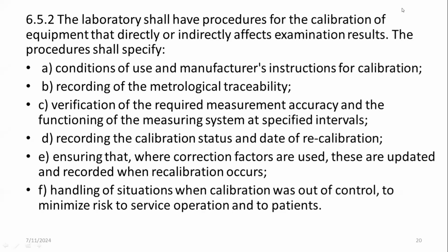So in summary, how this is supposed to be catered for is that once a calibration certificate is handed over to you, you're supposed to be able to determine what correction factors or correction values have been given by the calibration lab, and you should be able to use these correction values, as we shall see in the next slides. Then two, you're supposed to perform a verification to ensure that there is accuracy in the results that you're providing. Sometimes calibration may not be possible at that particular time, but in case it's not possible, what control is available to ensure that the service is still provided? So will you do a re-verification to ascertain that the equipment is still providing the right measurements?